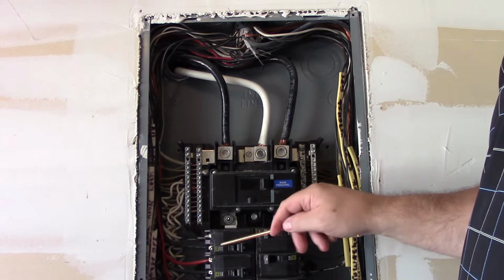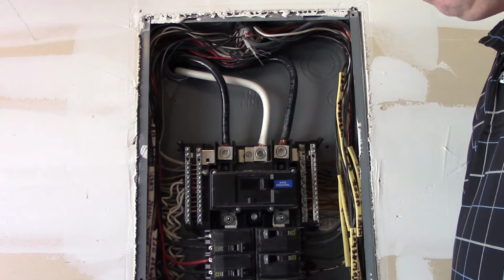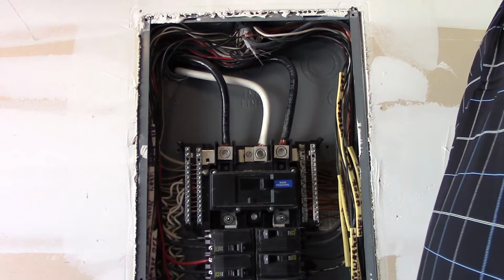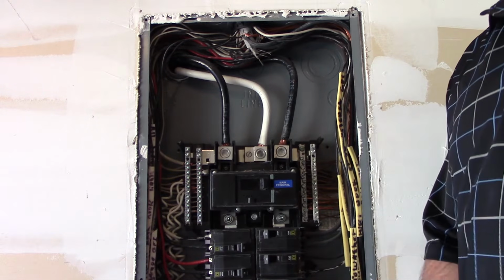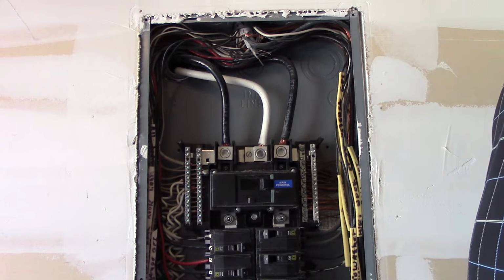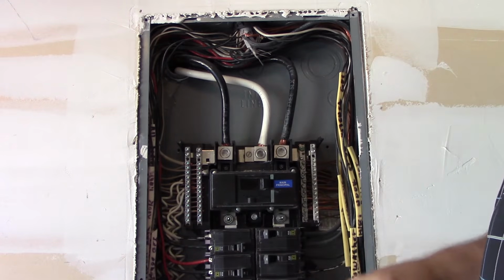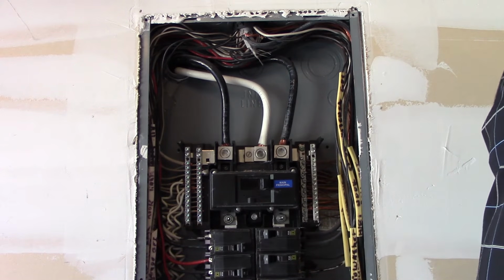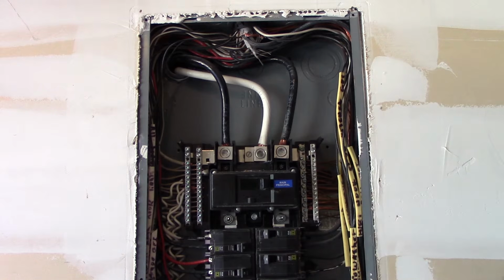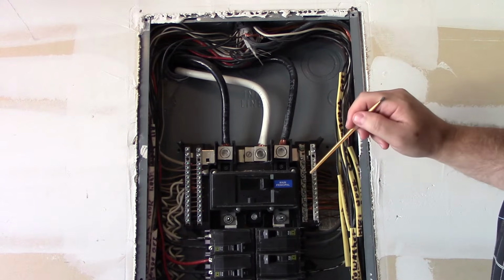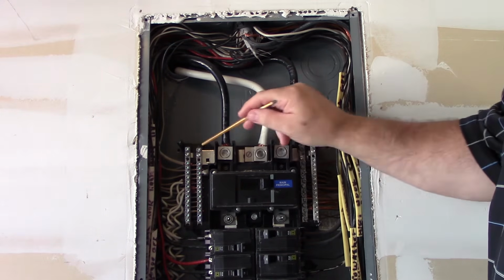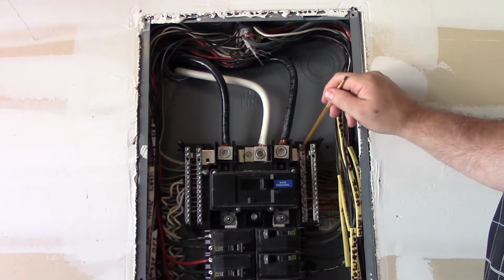So we'll have a breaker here that feeds a panel downstream somewhere, or out to a detached structure, say a barn or what have you, out in your yard. Then that's going to be called a remote distribution panel. This panel could be used in that application. The one thing you would have to do is remove this main bonding jumper. That isolates this bar from the metal enclosure when you remove this main bonding jumper.